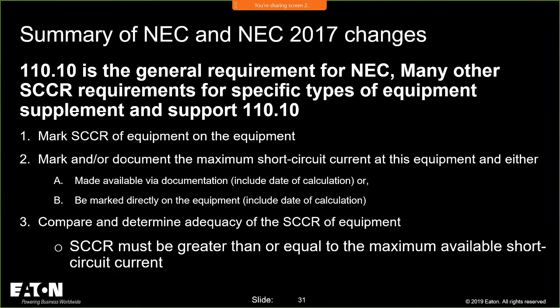The right recipe, in general, to properly make sure you are applying a product correctly with regard to available fault current is, first, you have to know and understand the rating of the equipment, and it's great to have that field marked. Second, you need to know what the available short circuit current is, and remember, it's the symmetrical fault current, maximum available at the line terminations of that equipment. And then third, you need to compare those two. The SCCR, the short circuit current rating, has to be greater than or equal to the maximum available short circuit current, and that is a symmetrical evaluated current that we're looking at, right?